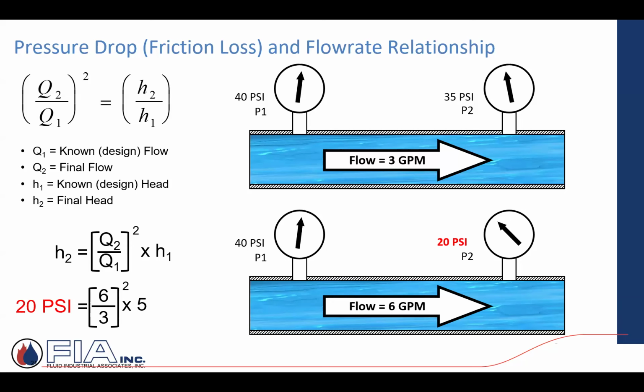I've got an existing system and I want to increase the flow. Recognize that as I try to do that, there's a squared relationship of that increase in pressure drop. I want to be aware of that. That's the beginning of just starting to understand pump curves and system curves, the relationship that exists. So when I change the flow, whatever that difference is, I square that number times my original design head loss. That will give me the answer to my new pressure drop.